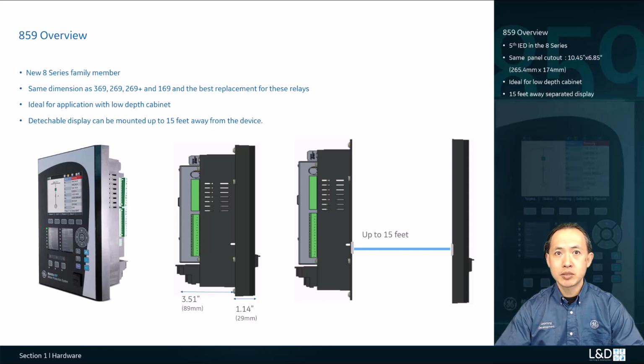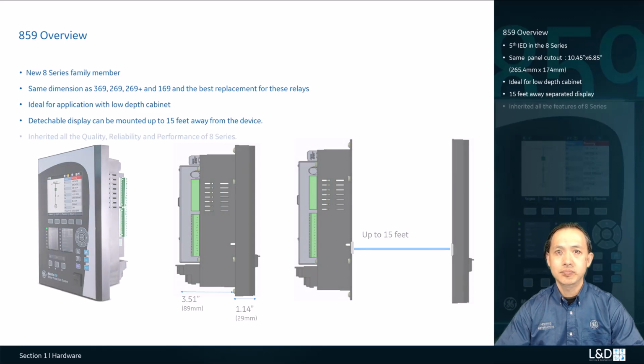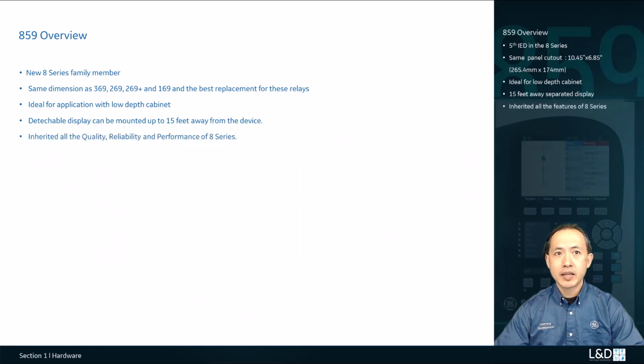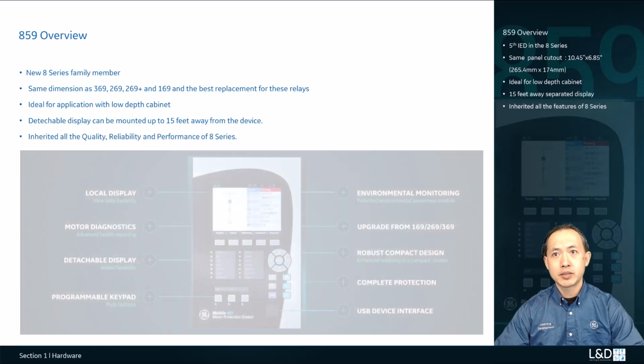Also, the detachable display can be mounted up to 15 feet or 5 meters away from the device with shielded network cable. No separate source of control power is required for the display module. This feature allows greater installation flexibility for space constraints. The relay will still function and protect the motor without the display connected. 859 can be considered the next generation of the Multilin 369 on the 8 Series platform.